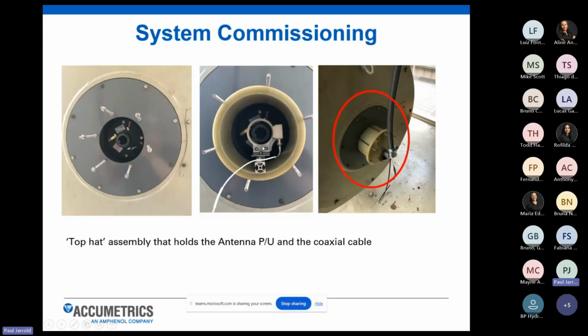This white ring is the stationary pickup antenna. That gets coupled both radially and axially around that snout of the rotating transmitter, and you can see the air gap of communication. So the dark gray transmitter would be rotating with the machine, and this white pickup antenna is stationary. Then we just have to connect one BNC cable off to our receiver unit to receive the field voltage and field resistance values. This is the same cable that we provide our induction power signal on to power the electronics in our rotating transmitter.